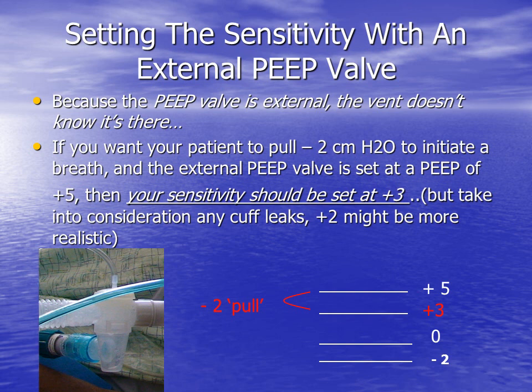But with the addition of an external PEEP knob set at, say, 5 centimeters, before the vent will allow a breath, the patient would have to pull below the +5 and then down the -2 for a total pull of -7 before they would get a breath. If you have a PEEP knob set at, for example, +5, and you really only want your patient to have to pull a -2 to get their breath, then you would set your sensitivity knob at +3.